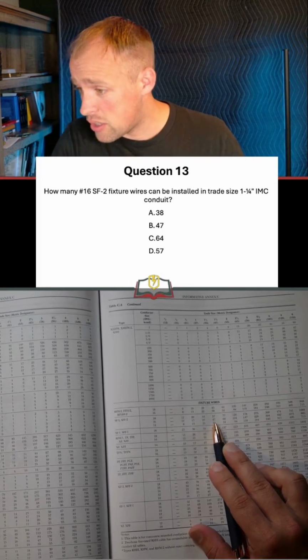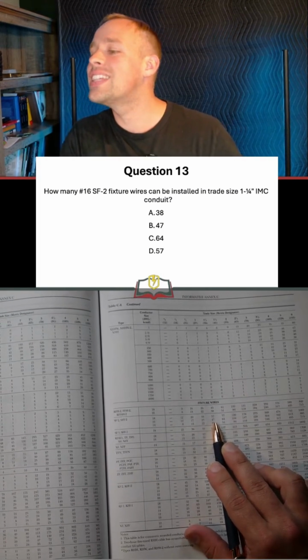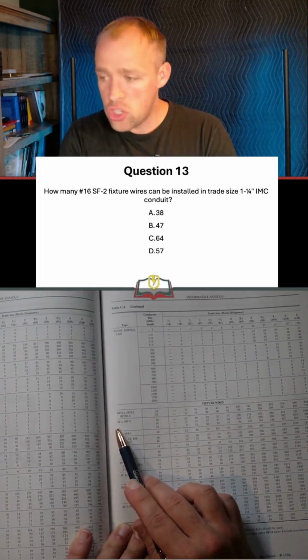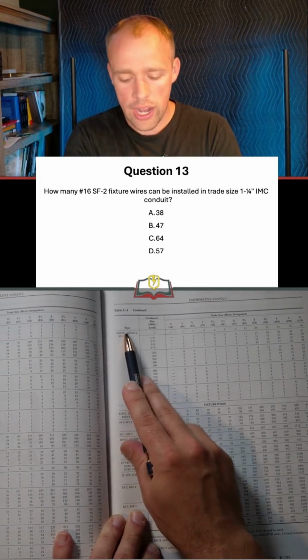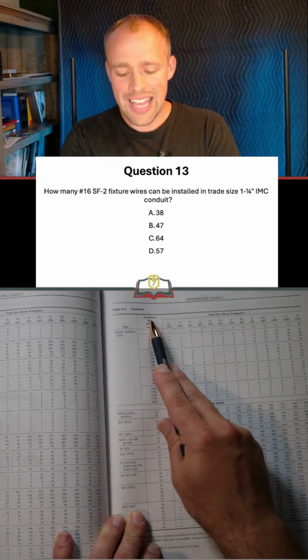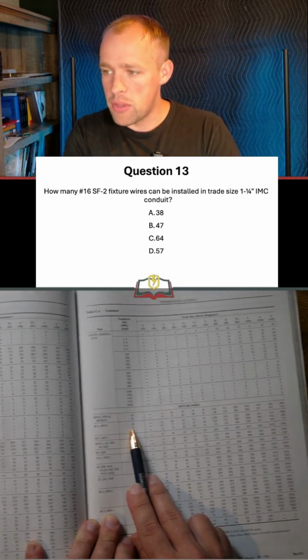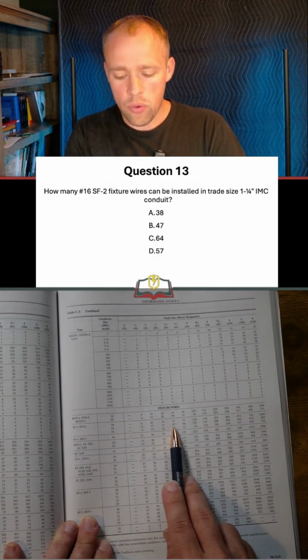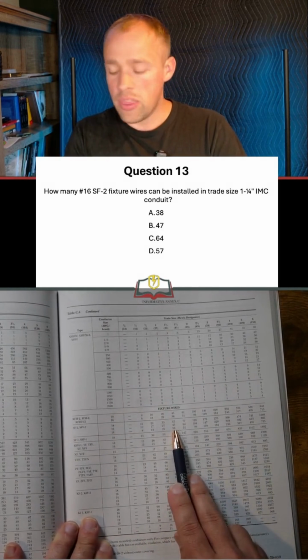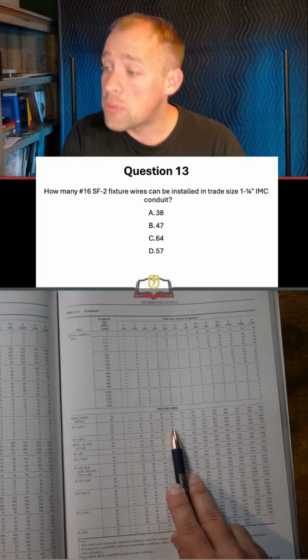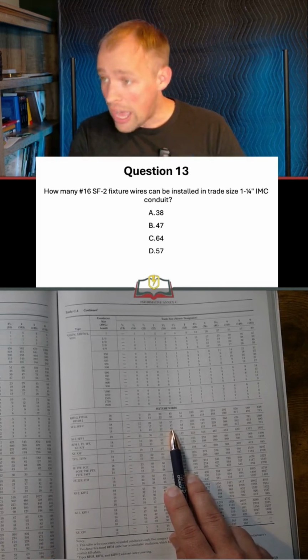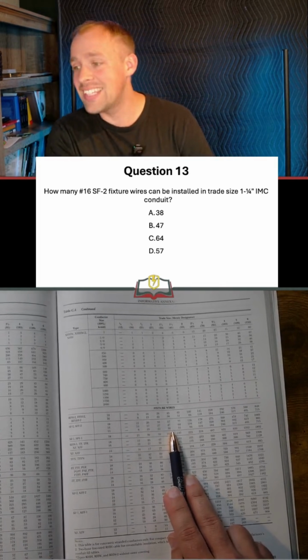Do you realize why the answer is not D? SF2 is our type of wire. Our size wire is 16, which is this middle row, and we have to line up our row with our column, and we therefore get 47, which is option B. Got to make sure that you can answer that question before licensing exam day.